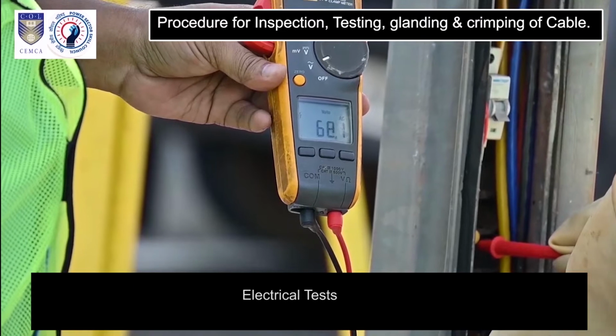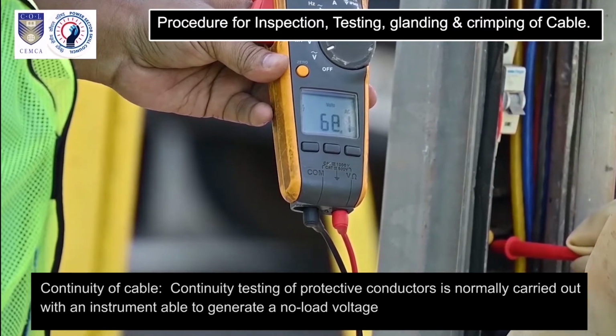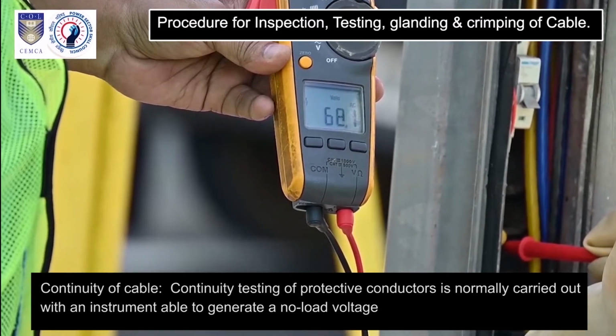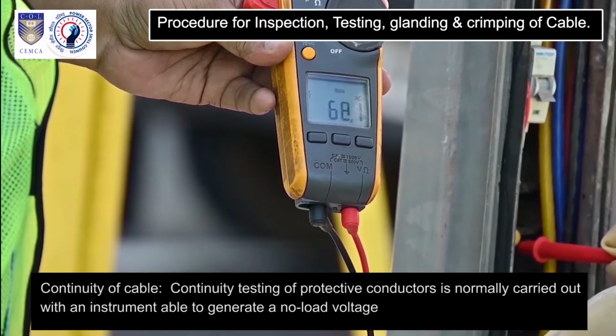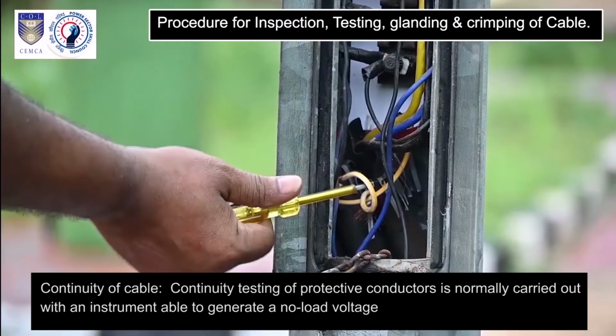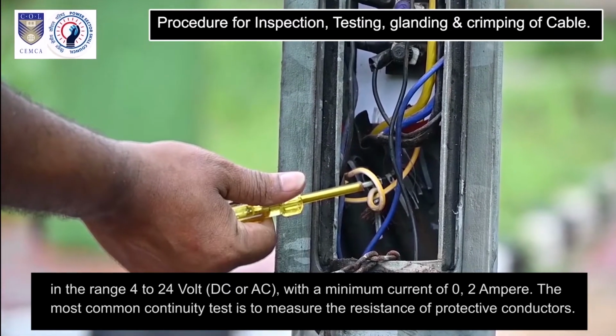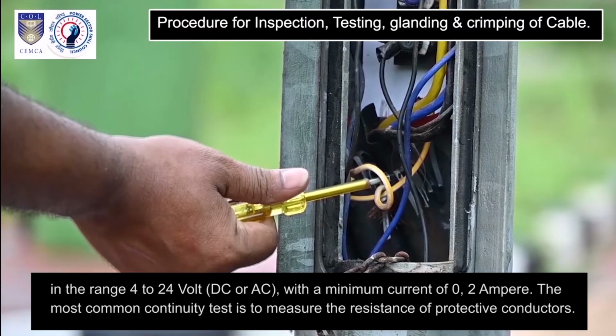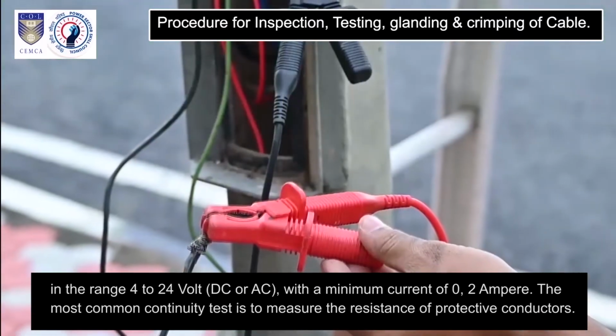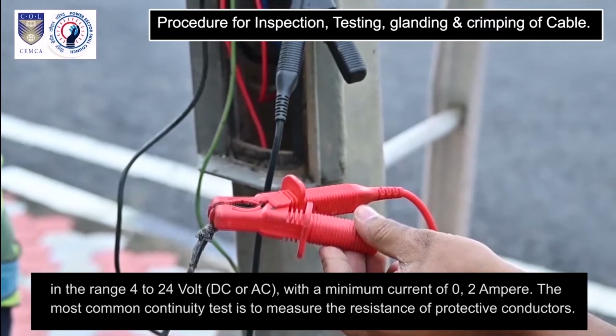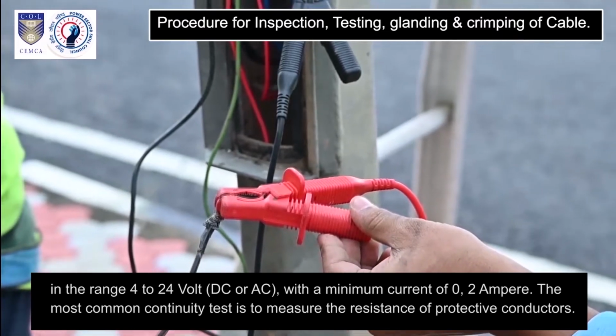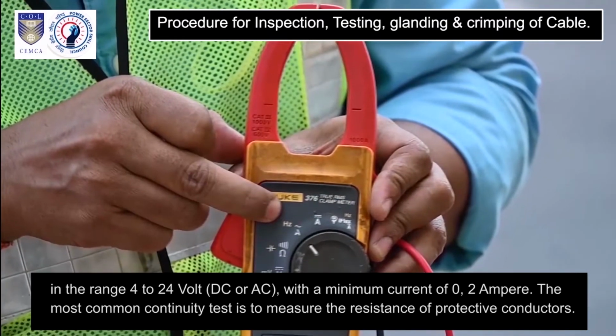Electrical tests. Continuity of cable. Continuity testing of protective conductors is normally carried out with an instrument able to generate a no-load voltage in the range 4 to 24 volt DC or AC with a minimum current. The most common continuity test is to measure the resistance of protective conductors.